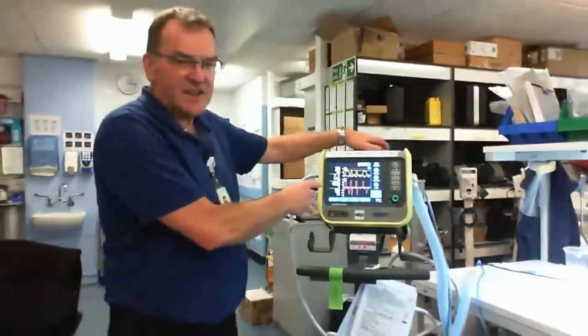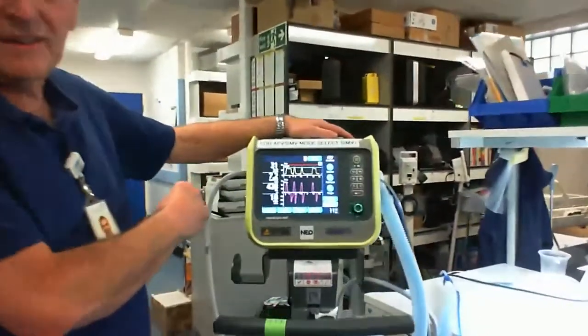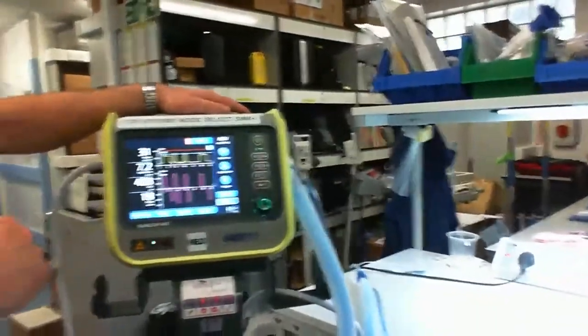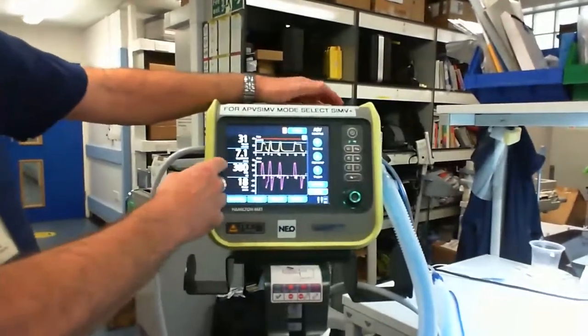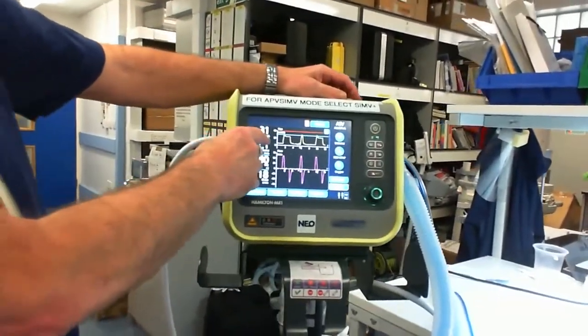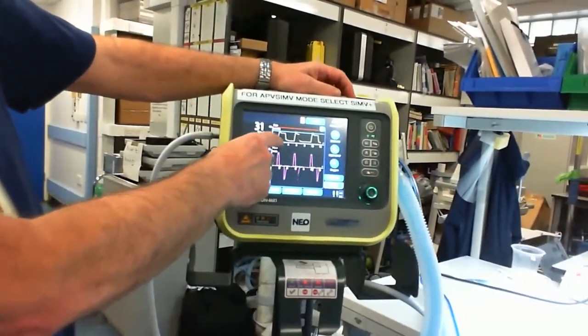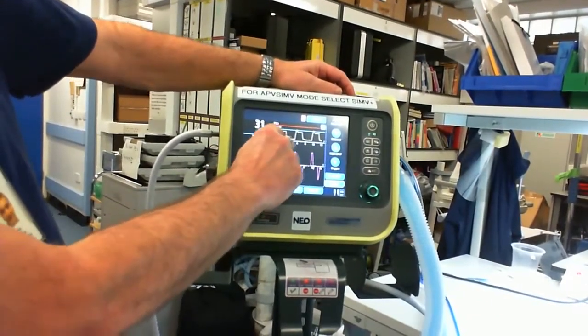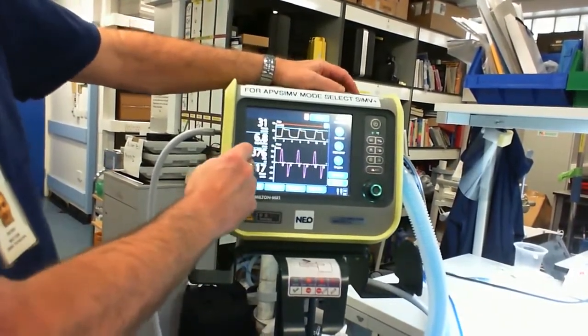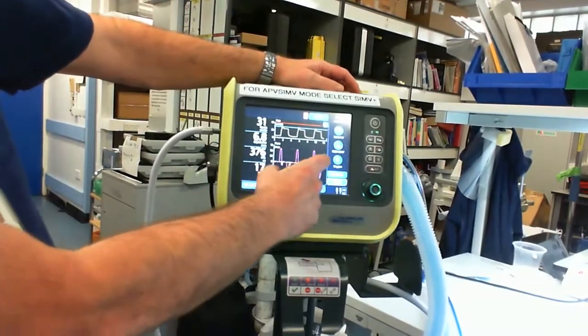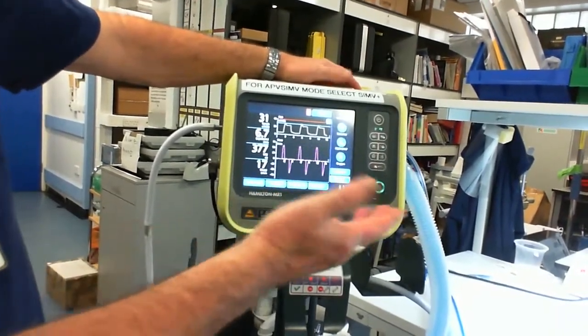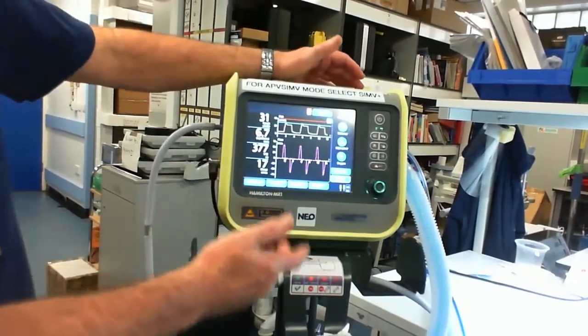As you can see on the ventilator here, there we go. Get a bit closer. Are we all right now? Yeah, you can see the waveforms. We have a peak-to-peak pressure of 31, which is shown on this top line, and we have a flow, which is shown on this line here. And you've got a total of 17 breaths per minute.